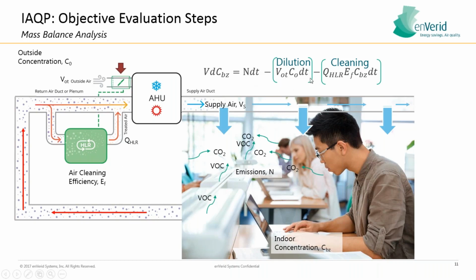And what you've traditionally done with the ventilation rate procedure is dilution. So with the indoor air quality procedure, you're still bringing in some outside air because you have to pressurize the building, typically somewhere between 5 and 8%. So you're still bringing in about 5 to 8% outside air, and that will assist with diluting some of these contaminants. And so this is basically your original VRP calculation right here, minus dilution.